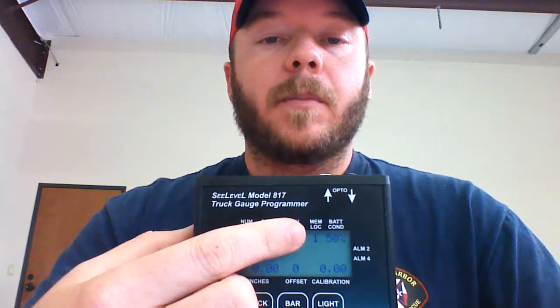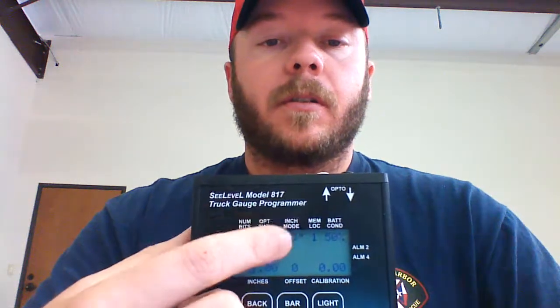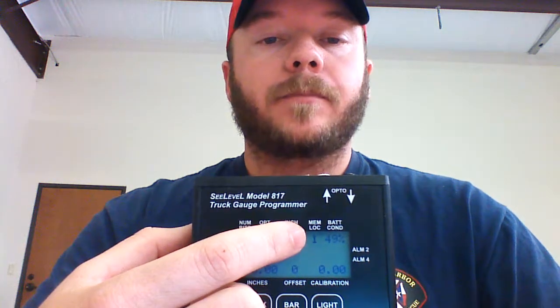And then moving on to the memory locations, you can store 8 different calibration charts with alarms in the programmer. So the mem loc here is which memory location that you're in. The battery condition is the battery condition of the programmer itself. At the top you have 2 screws. You can take those out. This faceplate slides up and out, and at the back there's going to be 4 AA batteries which are field serviceable. A note on the battery condition.